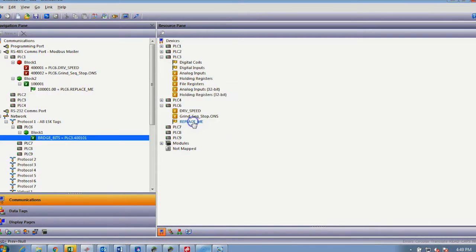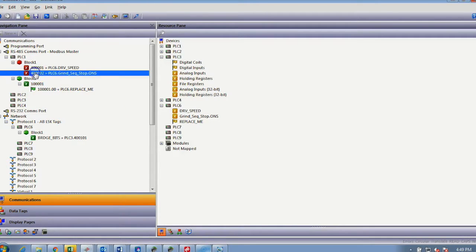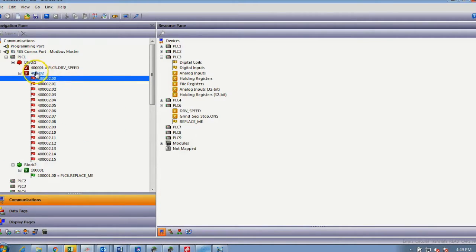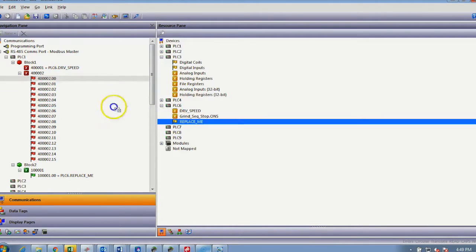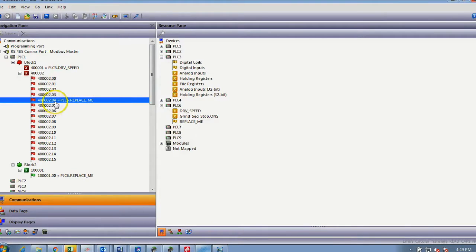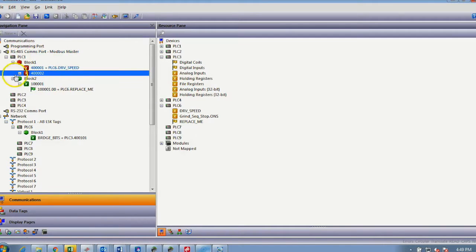Another very, very handy aspect of this type of mapping is if, from an Allen Bradley perspective, you wish to build an alarm word. You can, in Crimson 3, quickly expand this to bits. And I could, for argument's sake, drag bits in or out to build a word within another structure. So as you can see, the gateway block can be incredibly powerful.